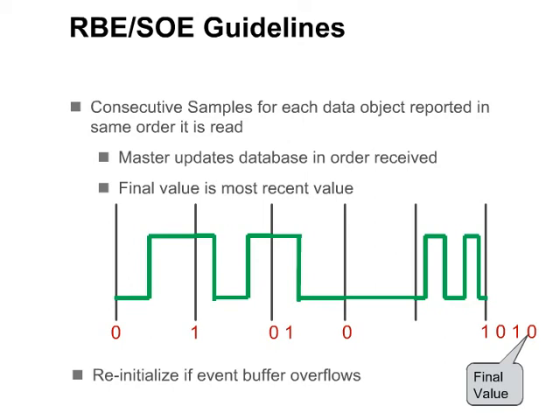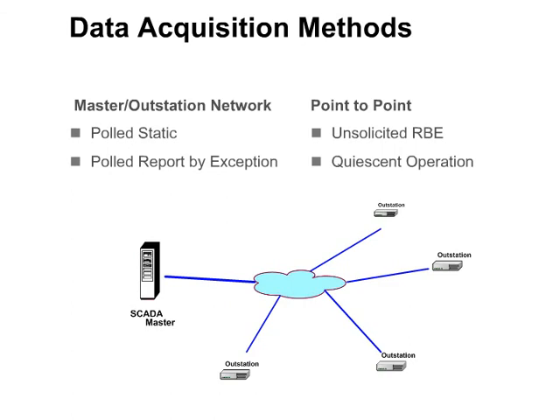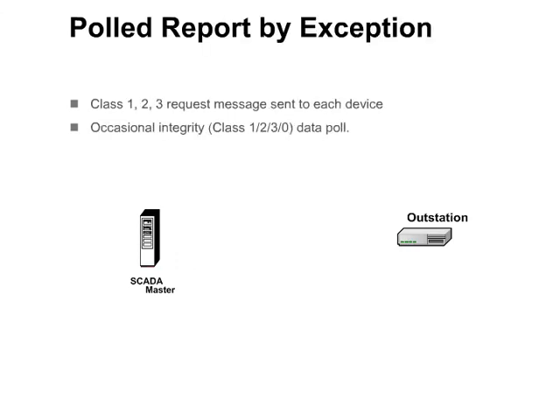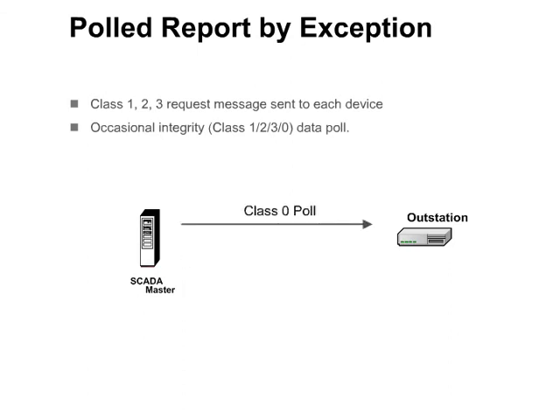DNP-3 supports multiple methods of retrieving data. Master-outstation networks typically use polled static or polled report by exception. In point-to-point networks, unsolicited report by exception and quiescent operation may be used. With the polled static data acquisition method, a class 0 or specific data request message is sent to each device and the device returns the requested data. With polled report by exception, a class 1, 2, and/or 3 poll request is sent to each device and the device responds only with the events for the requested class. An occasional integrity — class 1, 2, 3, 0 — poll is used to ensure that the database remains in sync.